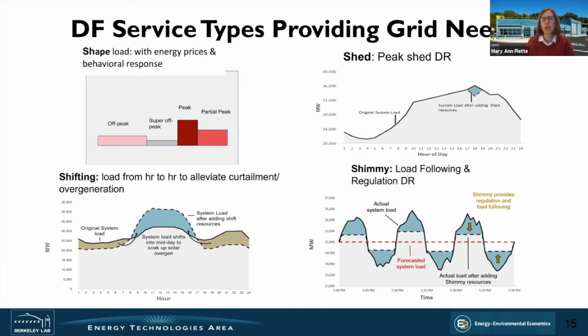That last bottom one on the right is what we call shimmy. The reason we called it shimmy is because we were looking for a verb: shape, shift, shed, and shimmy. We are shimmying the load, allowing it to follow some sort of faster signal, like a regulation signal that can help for voltage or frequency, or follow the load, or ramping. Some loads, like VFDs, can provide these shimmy services, and they can actually be energy neutral.